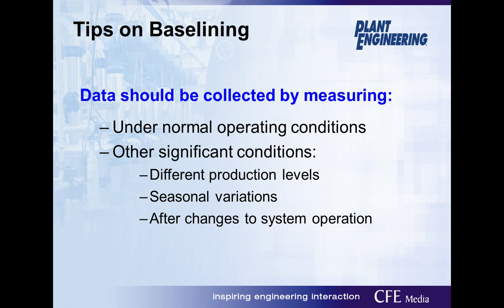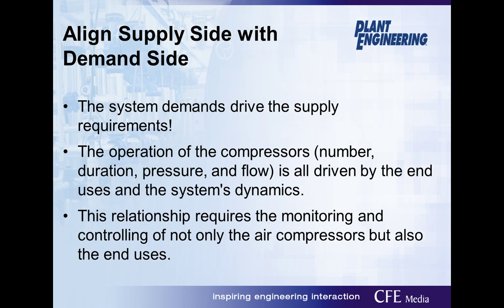Tips on baselining. We really want to look at the data under normal conditions and other significant conditions. That's going to be different production levels, whether it's a weekend, the difference between first shift versus second versus third, any seasonal variation. And then anytime you make a change in your production or your operation, add equipment, delete equipment, you really want to know what's happening in that baseline and make sure that you keep up with that.